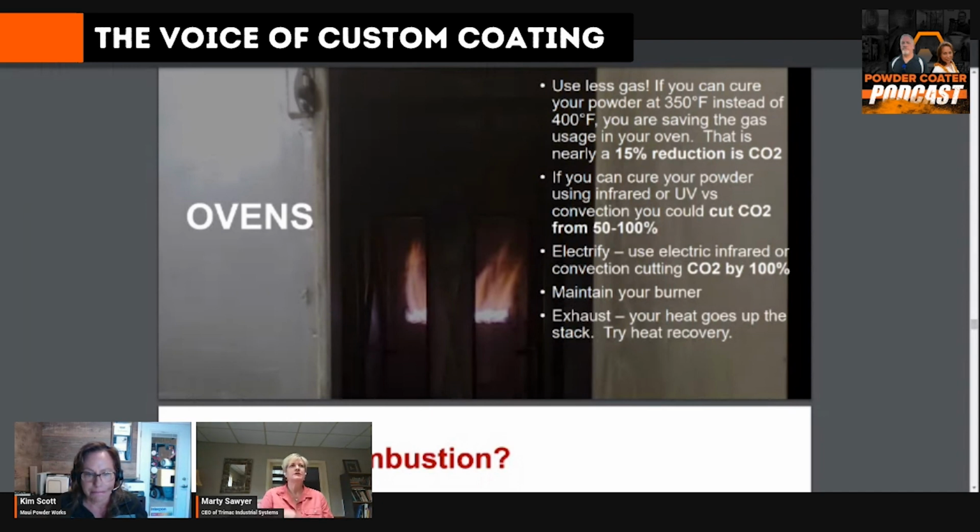Because the process is so fast to gel and cure, that's where the line of sight issue comes up: the higher temp you go, the less forgiving you are on line of sight. As you get into electric infrared, you're typically in the 1200, 1400, 1600 operating range, and thicks and thins become almost impossible without a lot of design criteria and a lot of babysitting. You can cure almost anything in catalytic, in large part because there's a lot of convection that happens intrinsically to the process, but also in the way ovens are designed.